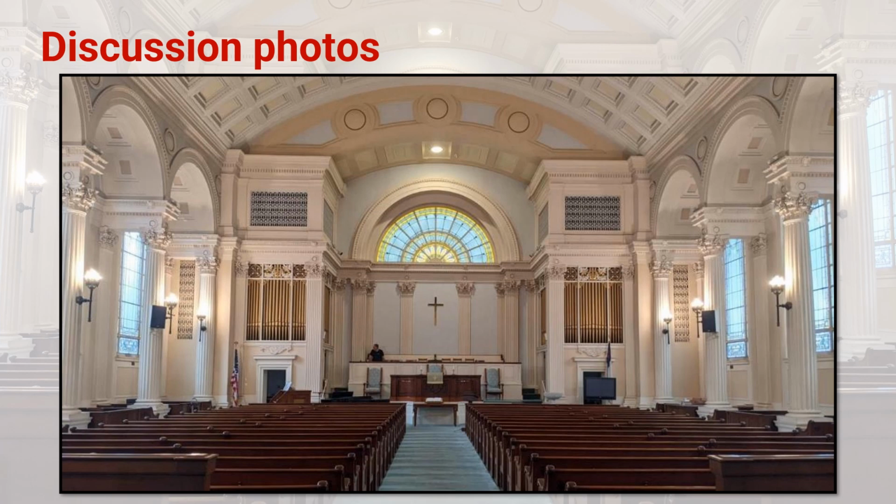choir loft way up on the ceiling there, we had to get to that through the attic, Indiana Jones style. That was a 400 watt metal halide high bay fixture above the ceiling, with the ballast 450 watts. So we replaced that with a 150 watt UFO fixture, LED, in warm white, and cut the wattage 75%, 80% right off the bat. So very, very nice savings from that. Also did the floodlights, or the spotlights, on either side of the choir loft, which are not on in this photo, but you brightened it up quite a bit and cut the energy use considerably. So just a demonstration of what can be achieved.